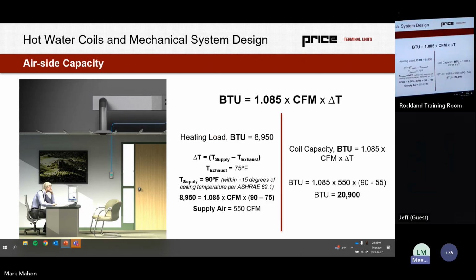So I like to look at the actual calculation. And once again, this is kind of cookie cutter ASHRAE stuff, but it helps paint the picture. So what I'm looking at is a zone heating load of 9 MBH roughly. And if I'm assuming some temperatures like a 75-degree exhaust and a 90-degree supply air temperature, which is within a 15-degree delta T, which is going to mean essentially that I have a good ventilation effectiveness in design day heating conditions, I could be looking then at a supply air of 550 CFM to offset that load. 550 CFM of 90-degree air is going to keep my space comfortable on design day.